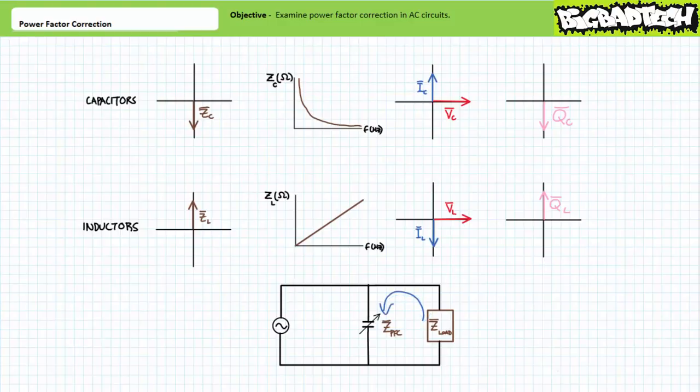At the opposite end of the cycle, the moment when the inductive magnetic field is collapsing and squeezing out current of a given magnitude, the power factor correcting capacitor is charging and sucking in this exact same amount of current. In this sense, the inductive portion of the load is dumping all of its stored power into the power factor correcting capacitor just when it needs to get rid of it. This is perhaps the origin of the terminology absorb and supply with respect to reactive power.